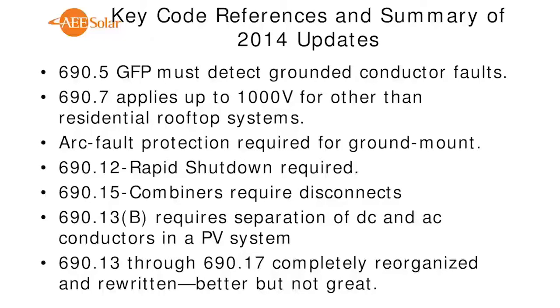So today is advanced topics. We talked about basics yesterday. IV curve, got to know it. Changes current and voltage with temperature and irradiance. But we're going to jump down to the changes in the code. So we talked about some of the changes in the 2011 code, which was routing identification, arc fault detection, did a little reorganization, moving some things into 705, which is why we have to talk about 705 now. And then in the 2014 code, we got specific about how to detect ground faults, raised our voltage levels for low voltage up to 1,000, changed some of the arc fault detection requirements for ground mount, added ground mount requirements.